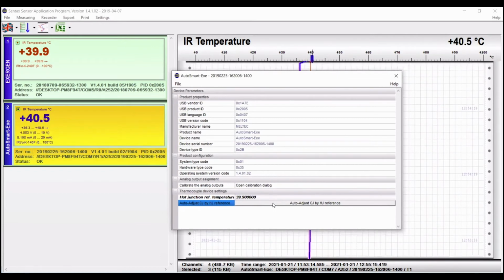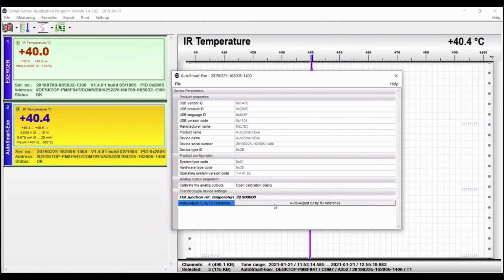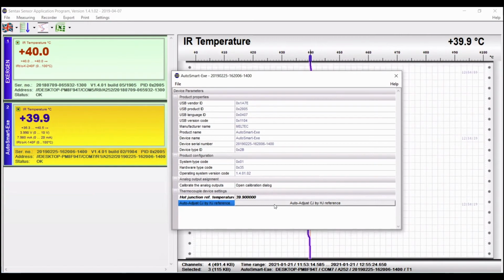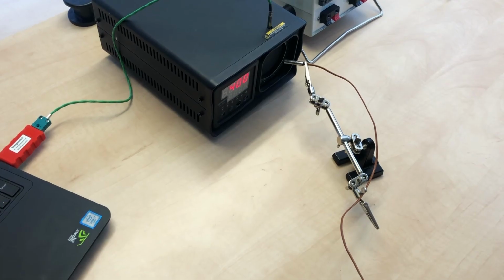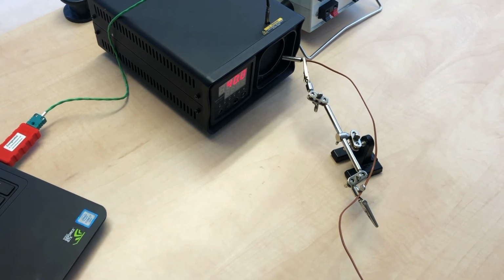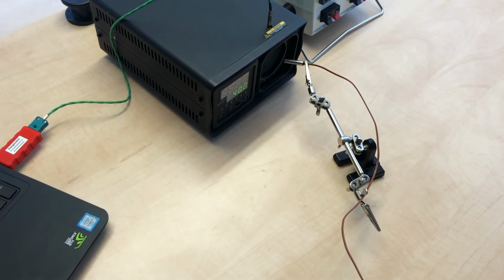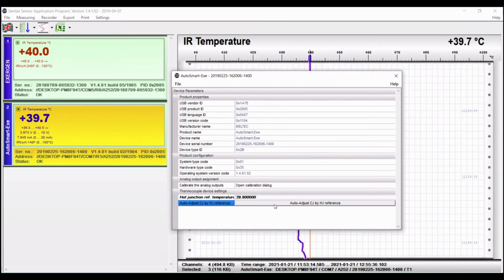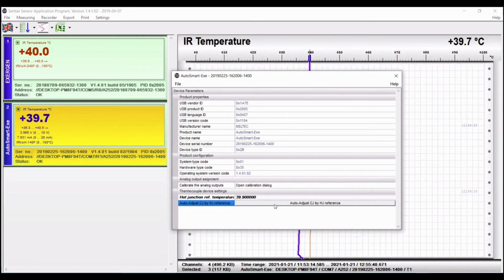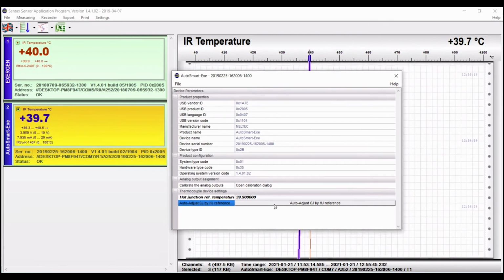And then you will see the AutoSmart transmitter will automatically adjust the sensor reading to go to the set value of 39.9. And now, even though the sensor itself might be reading a slightly lower temperature because of field of view issues, it still gives a very accurate temperature reading as compared to the reference. And as long as in any application the environments are reproducible, the sensor will give you reproducible results. So now this sensor is custom calibrated.